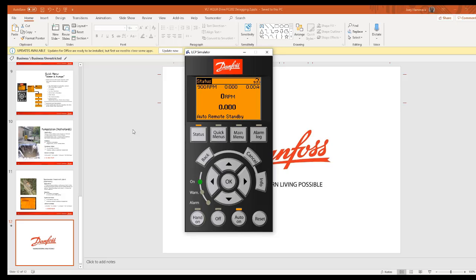No, I can't, I can set the power automatic thing, but maybe he doesn't want the drive to determine when the DERAG. Since they already have a SCADA, he wants the SCADA to monitor current, and seeing a high current condition, he wants to trigger DERAG. And that's what I was looking at, digital input, and we can. Let me check the programming guide and see if it's linked to a certain digital input. Then I would like to answer that question because I know I've triggered it.